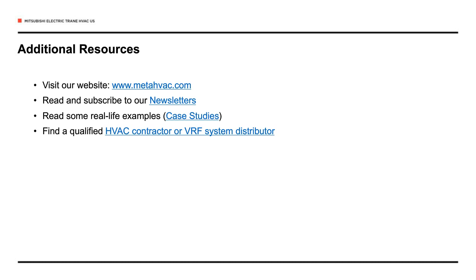We have found it to be generally in the same ballpark as water source heat pump systems. The AC Marriott had some unusual circumstances that helped VRF look even better. But generally, we see that compared to traditional water source heat pump systems, VRF is usually a little bit less expensive, but kind of the same order of magnitude. So a lot of it depends on what the conventional system is that it's being compared to.